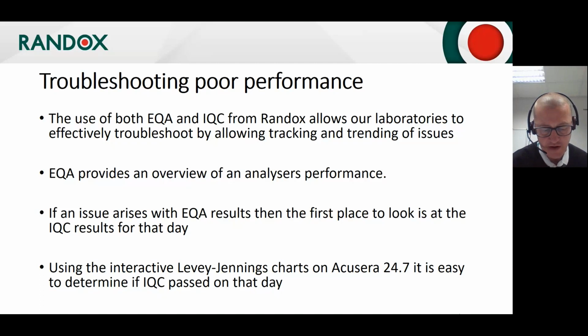EQA provides a thorough overview of an analyzer's performance against known targets. If an issue arises with EQA, then the first place to look is the IQC for that test on that day that the EQA was run. This is easily done using the Levey-Jennings plots. As I said earlier, you can put in a specific date range. So if you know the date that you ran your EQA, you can just look at the results for that day. And if your results are fine, then it might be that it was showing an alarm, such as a warning or a trend, or even if it had failed, but someone still ran the EQA, it might have been that it's the last day, deadline submission day, so it gets run anyway.